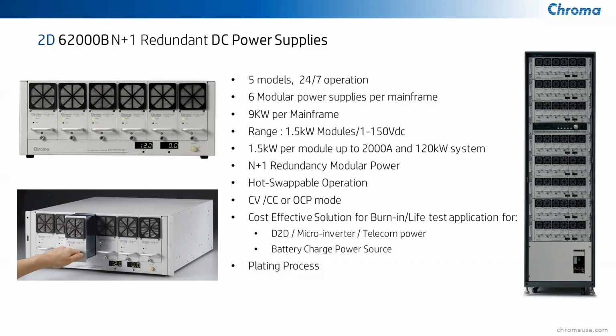Over long durations, if anything happens to occur, these units are hot swappable, meaning that you can extract the unit while all the units are still operating without interrupting the power to your device under test. You can take it out and plug a new unit in, take it out, service it, or plug it back in without any interruption at all. These units also operate in constant voltage and constant current. They also have overcurrent protection modes, and they're used greatly in what we refer to as life testing and burn-in testing for DC to DC converters or micro inverters that have a DC input. And telecom power, 48 volts, distributed power, a lot of DC to DC converters in the distributed power. So perfect for those kinds of tests.